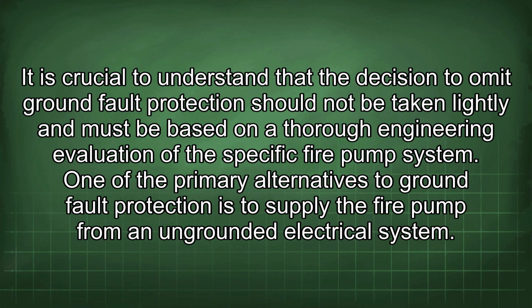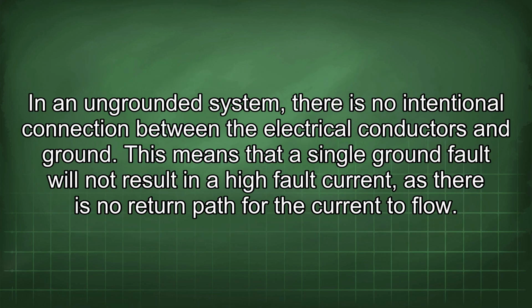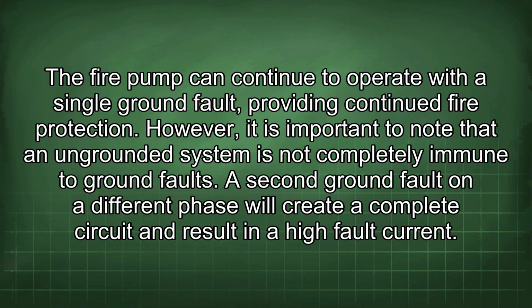One of the primary alternatives to ground fault protection is to supply the fire pump from an ungrounded electrical system. In an ungrounded system, there is no intentional connection between the electrical conductors and ground. This means that a single ground fault will not result in a high fault current, as there is no return path for the current to flow. The fire pump can continue to operate with a single ground fault, providing continued fire protection.